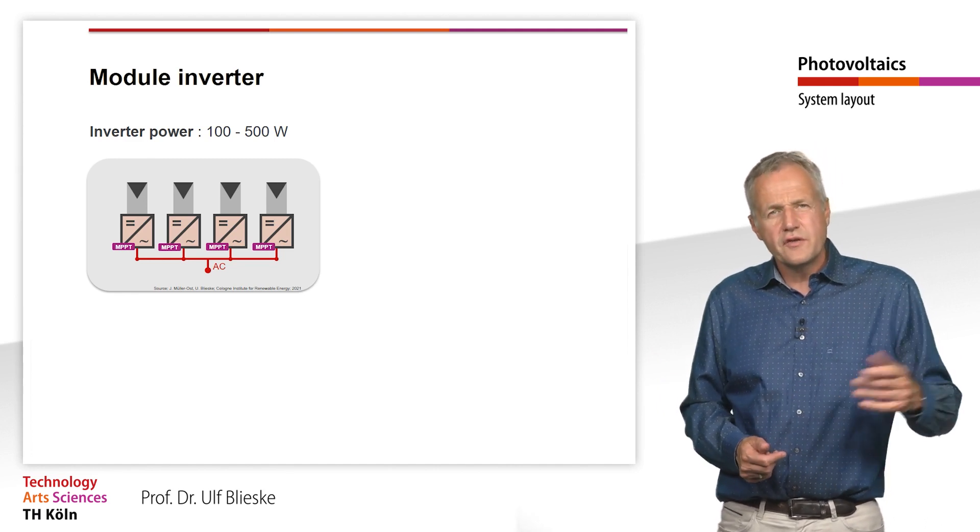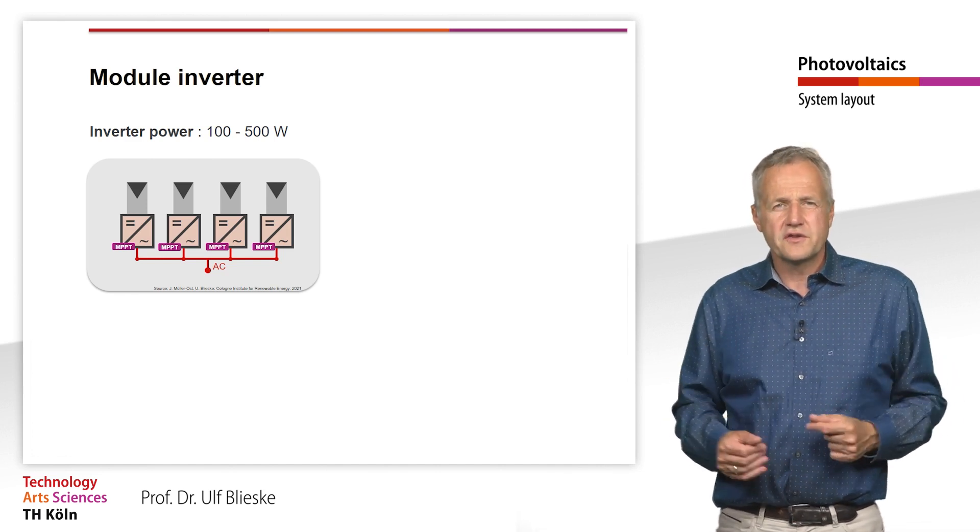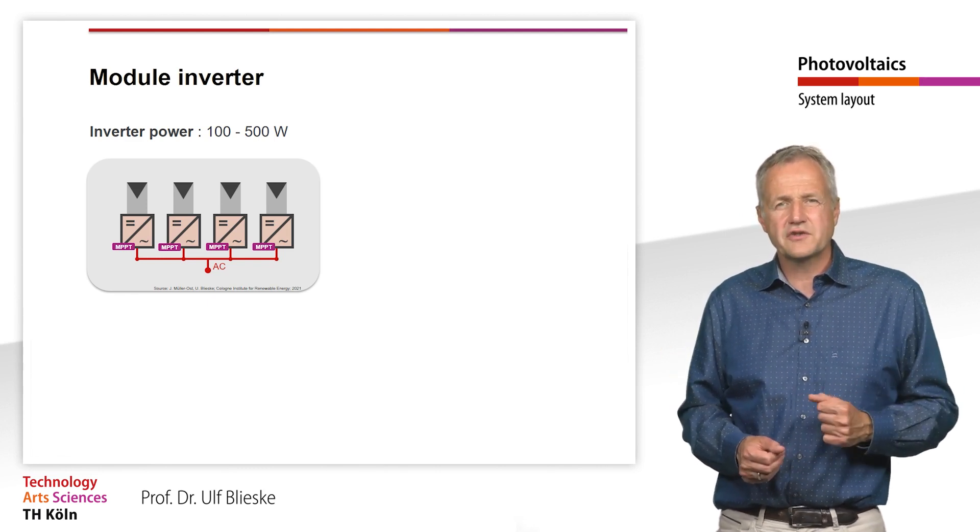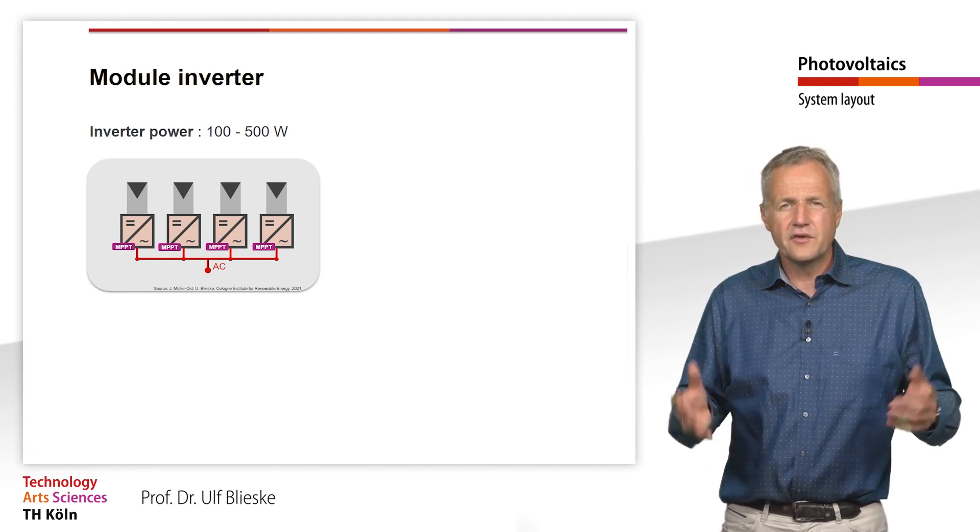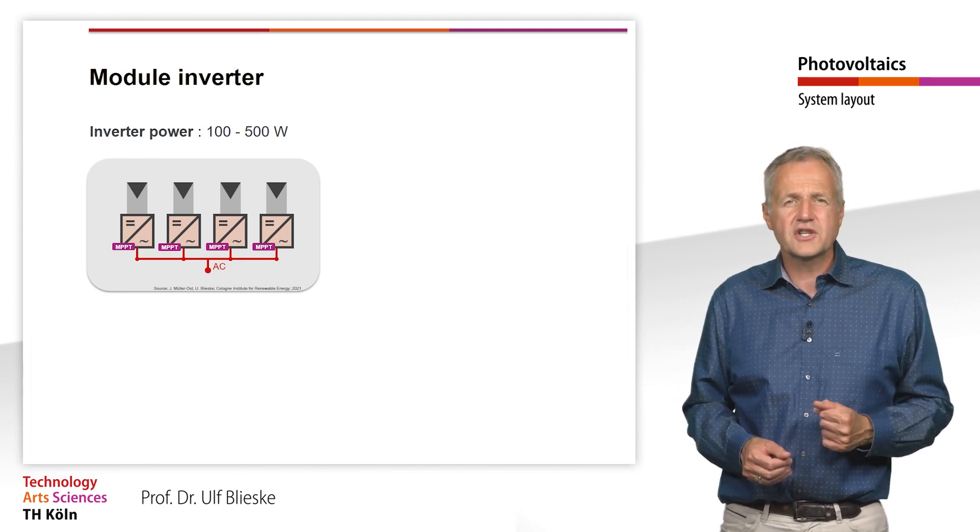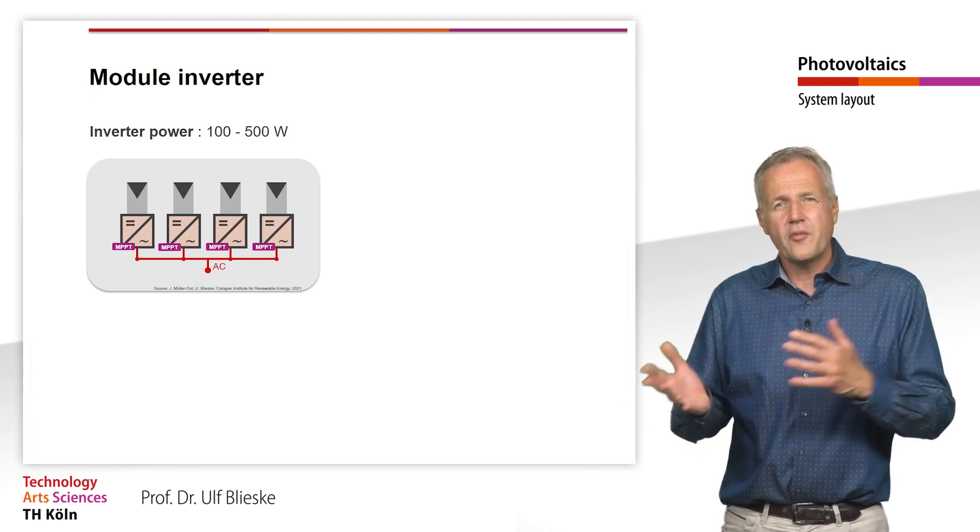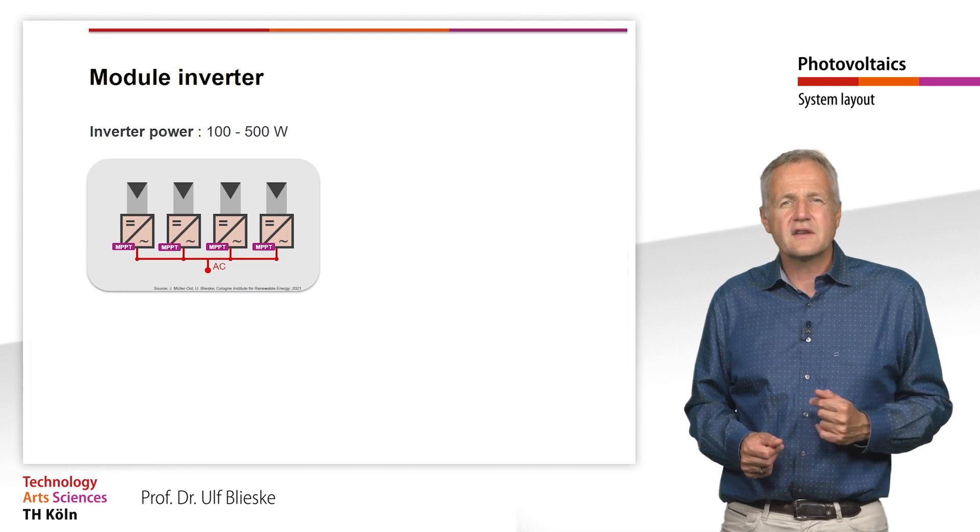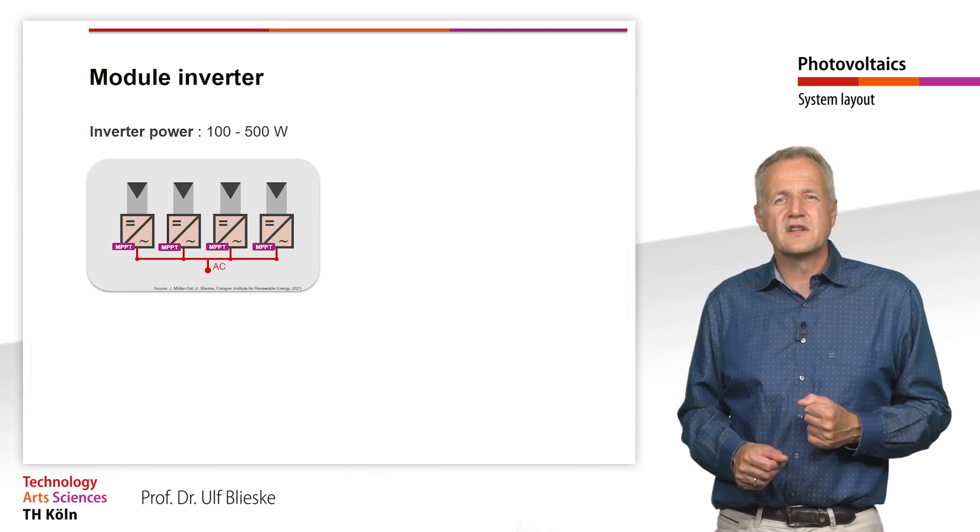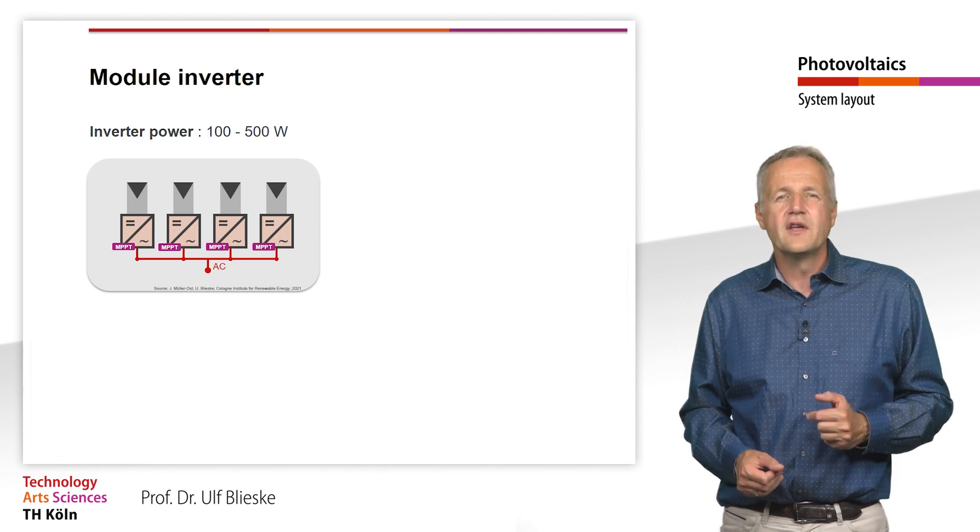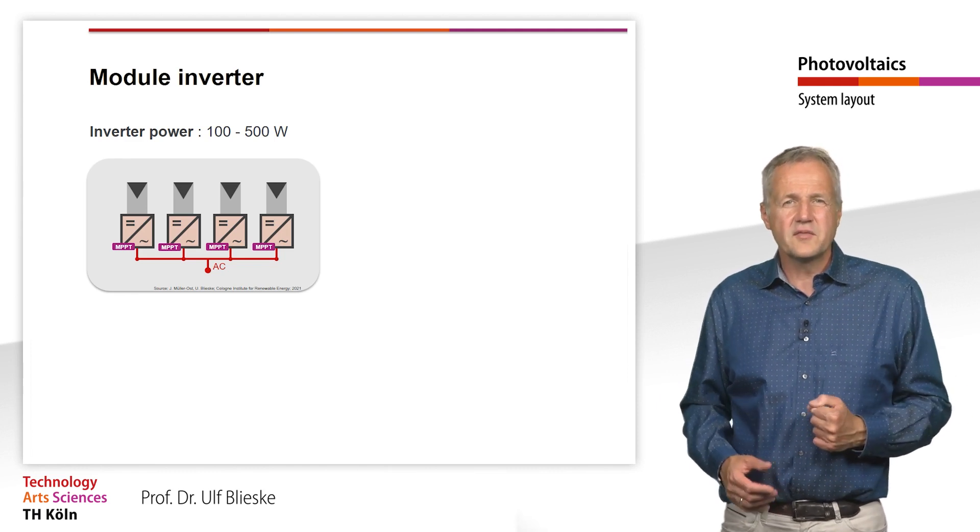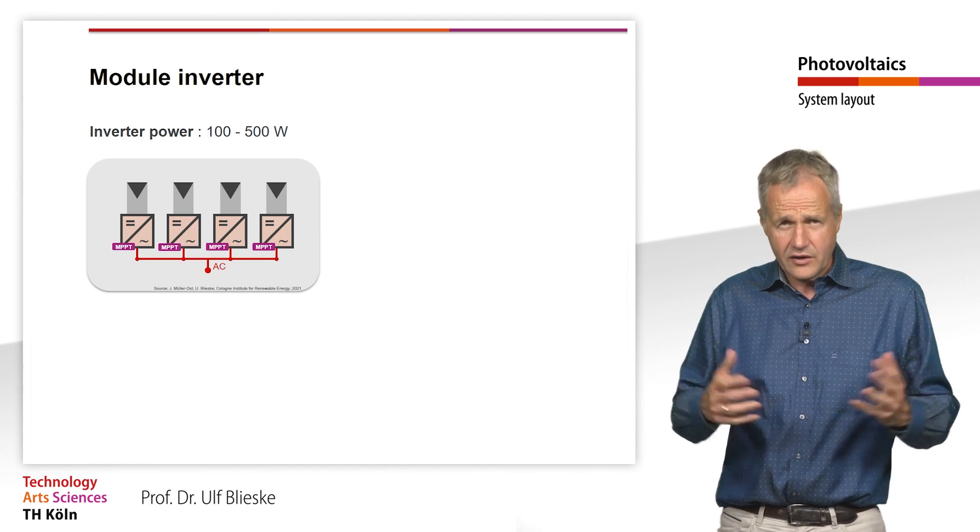One major problem with module inverters is that they are mounted on the roof with the modules. As a result, they are exposed to wind, weather and above all high temperature fluctuations, which greatly affects the service life of the module inverters and can lead to premature failure. In any case, the lifetime of an inverter is much shorter than that of a PV module, whether it is a string or module inverter. It can be assumed that an inverter needs to be replaced after about 10 years. The replacement of a module inverter is possible, but due to the installation on the back of the module on the roof, it is associated with a significant effort. While this can still be done easily with small systems, the effort increases with increasing system size.